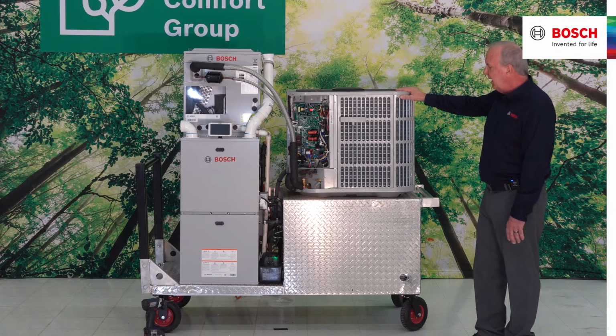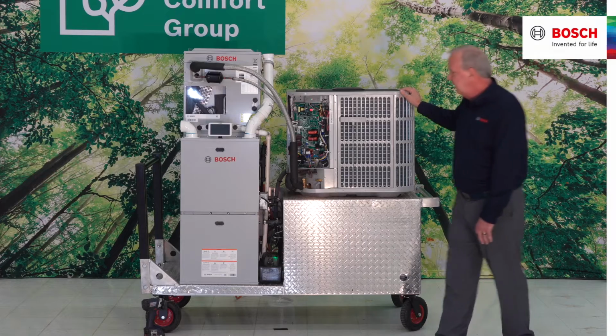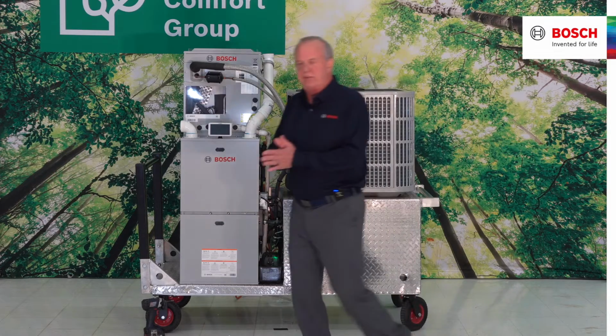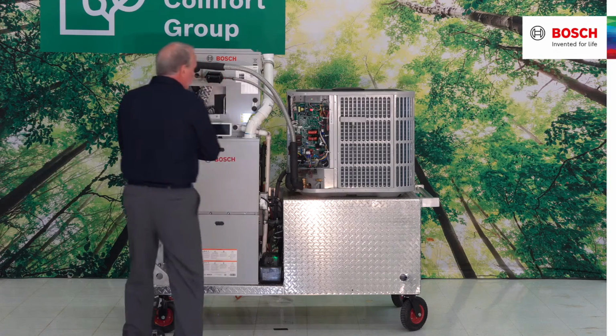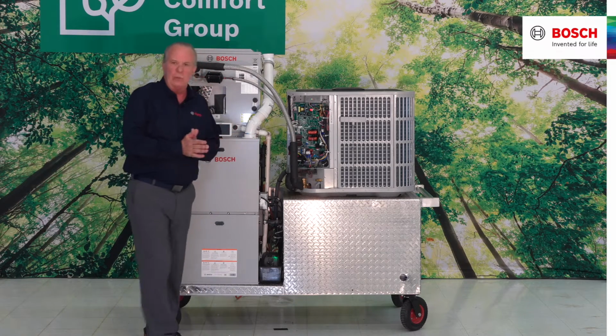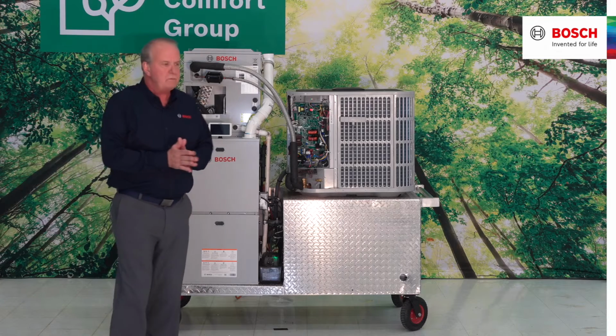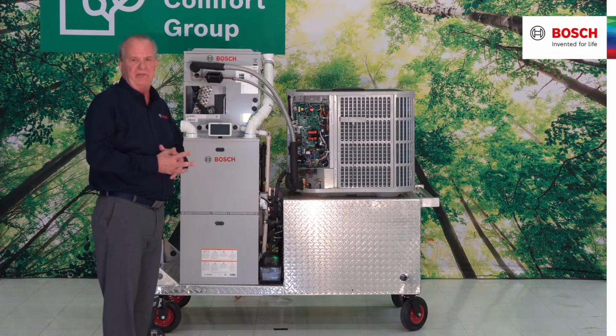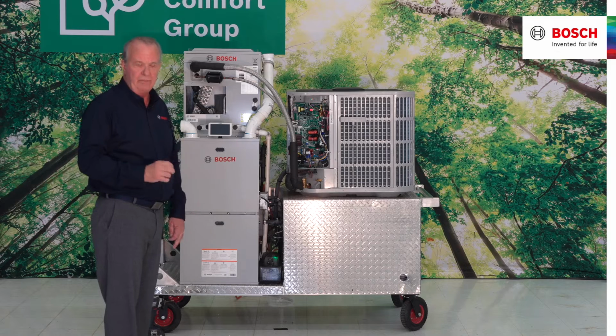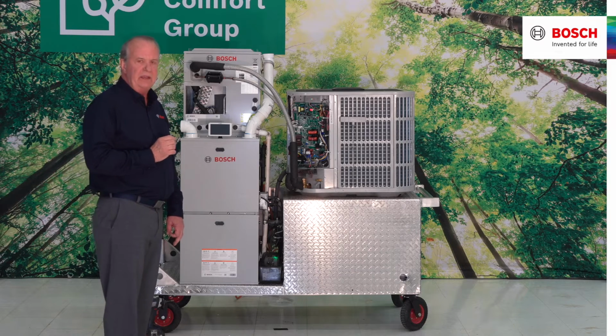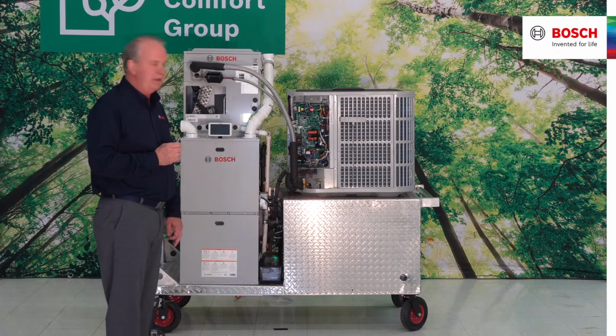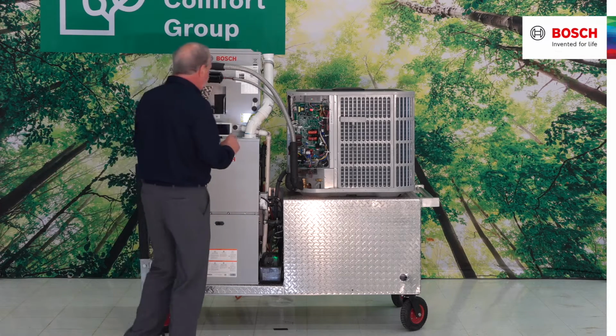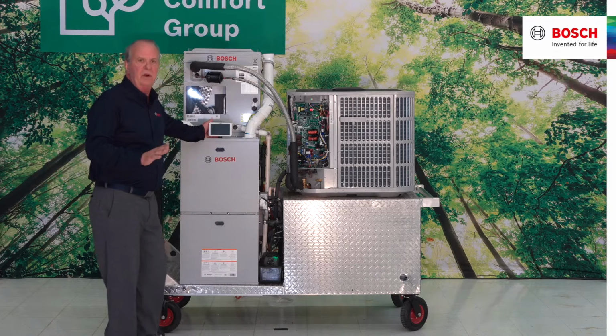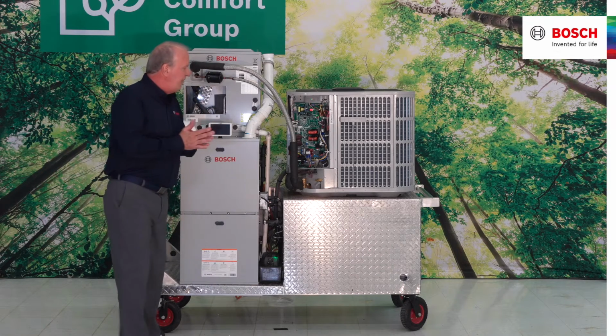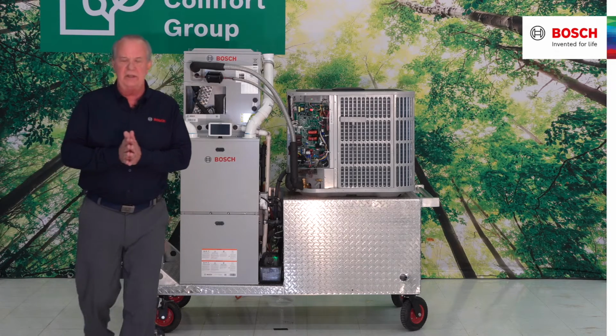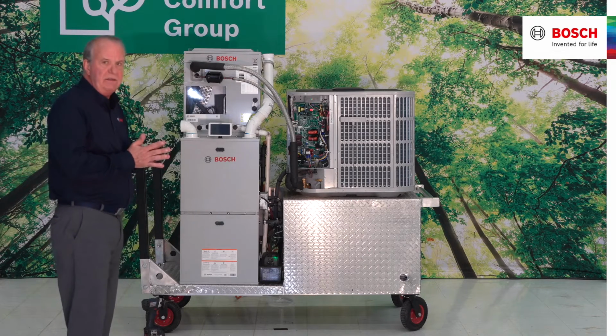This piece of equipment, as all of our pieces of equipment, is what we call a critically charged system. We want to charge this system by liquid line length and diameter. All of our equipment, the 2, 3, and the 5-ton, use a 3/8 liquid line. There's no exception to that. That is a critical component of the installation and operation of this equipment. 3/8 liquid line on all of our equipment, no exceptions. The factory charge that comes in our unit is good for 15 feet of liquid line.